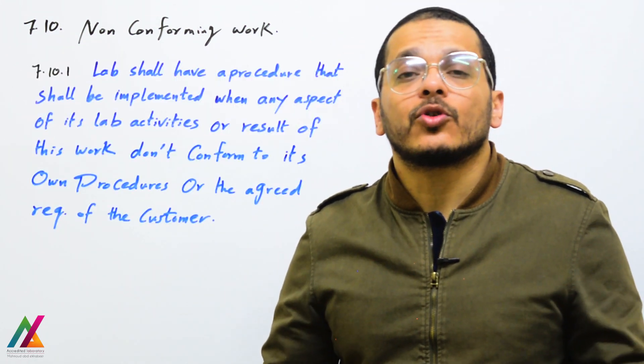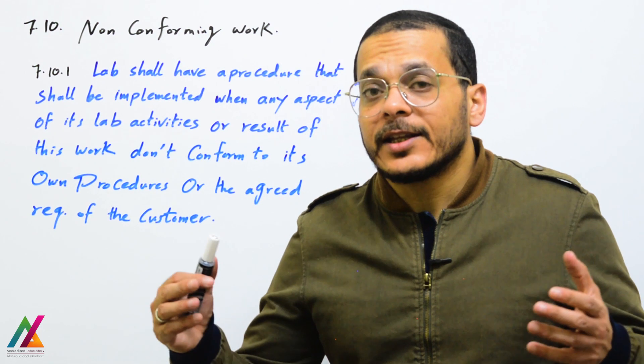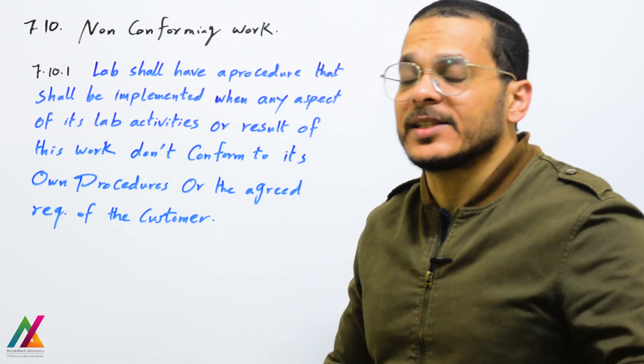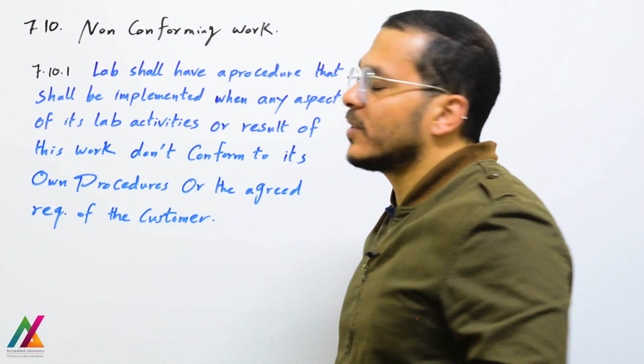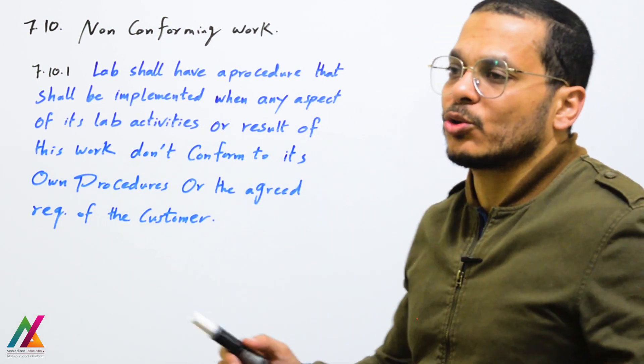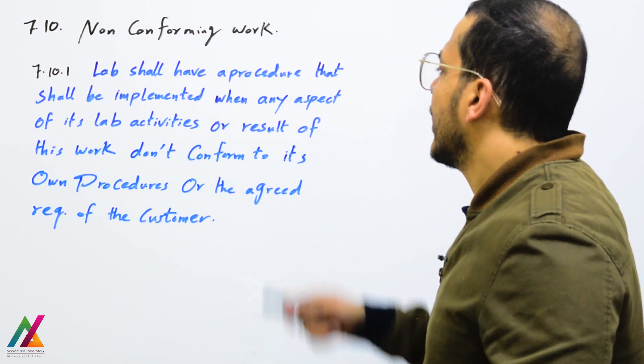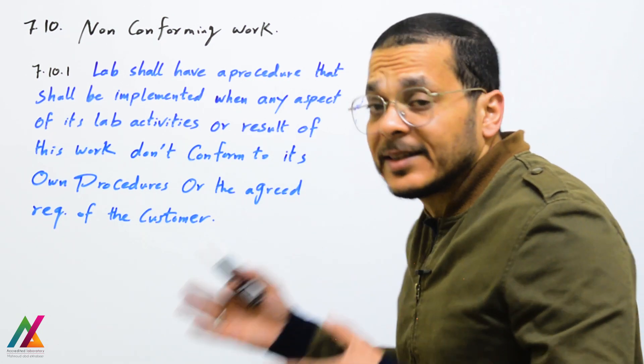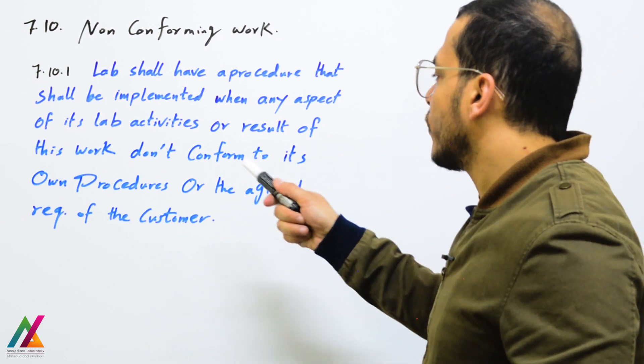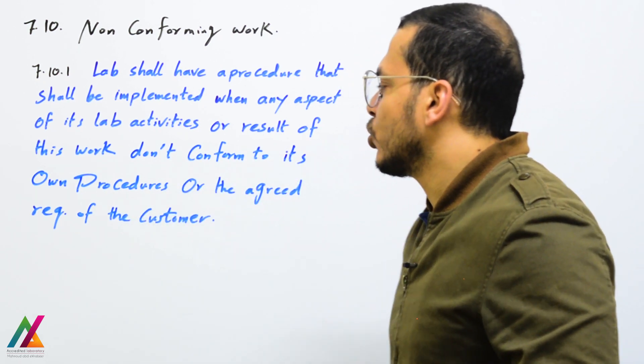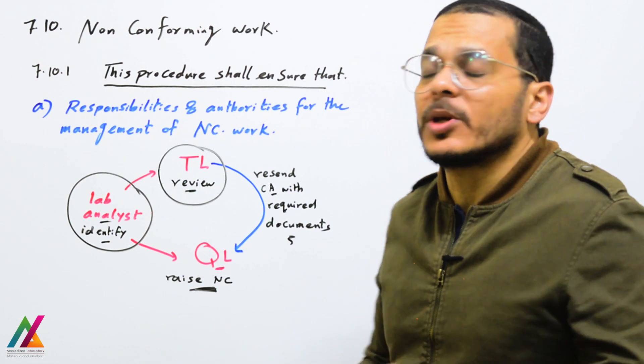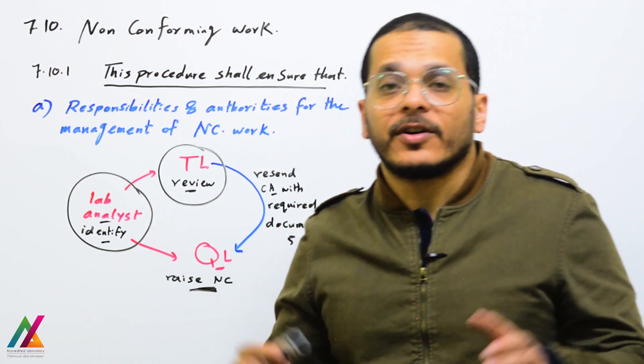After understanding non-conforming work — what it means, the whole process for solving non-conformity, and the responsible persons at every step — the requirement of ISO/IEC 17025:2017 states: the lab shall have a procedure that shall be implemented when any aspect of its lab activity, testing or calibration work, or the result of this work, does not conform to its own procedures or the agreed requirements of the customer.